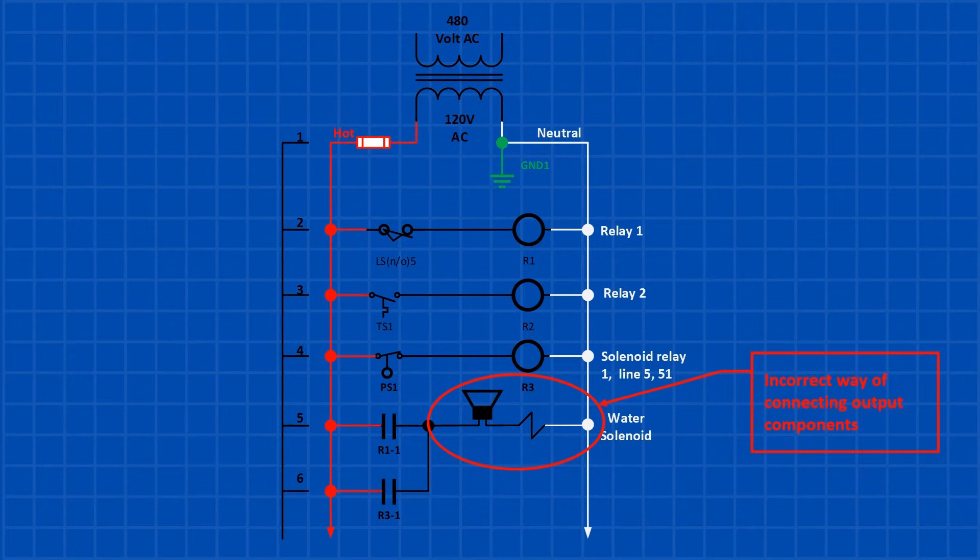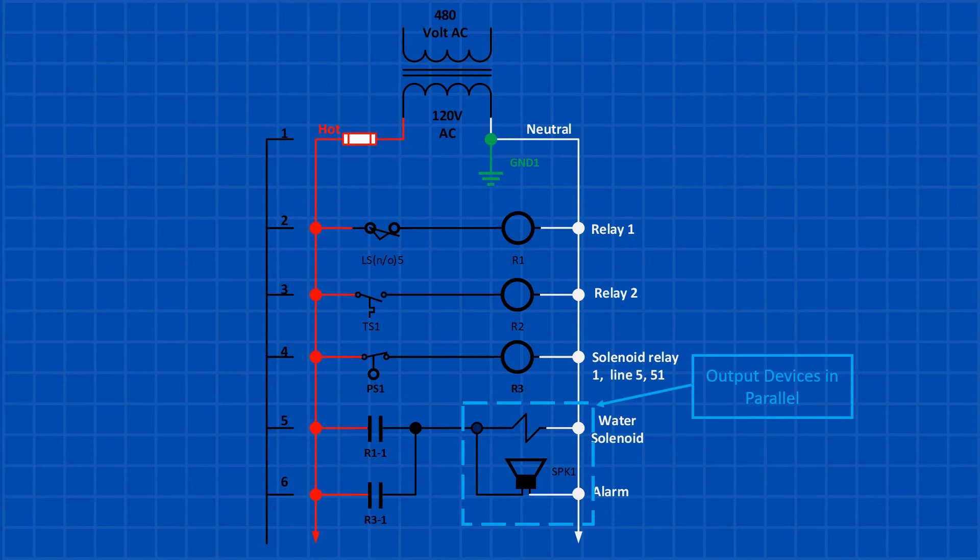Output devices should never be connected in series. Doing so causes a voltage drop across each device, preventing them from functioning properly. Instead, they should be wired in parallel. For example, on lines 5 and 6, the water solenoid and alarm speaker are correctly wired in parallel to ensure proper operation.